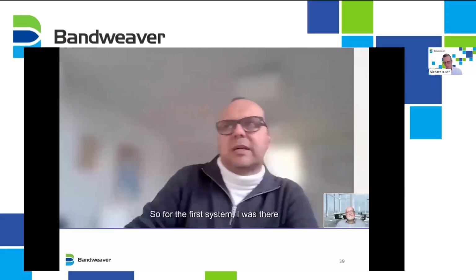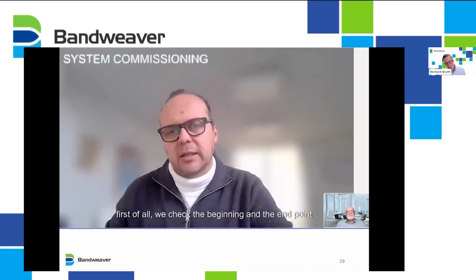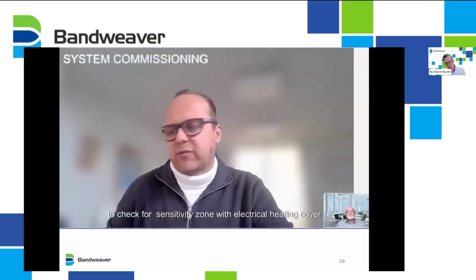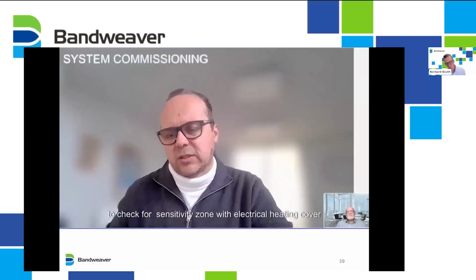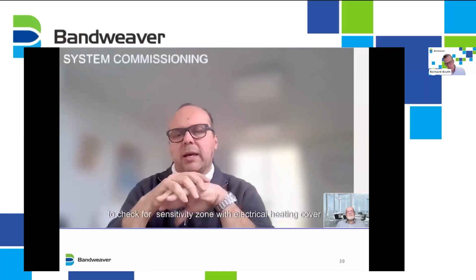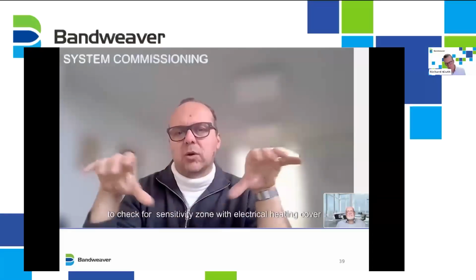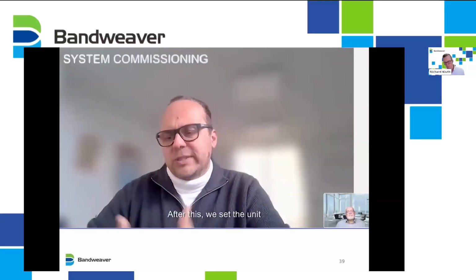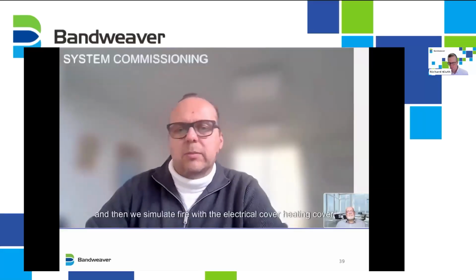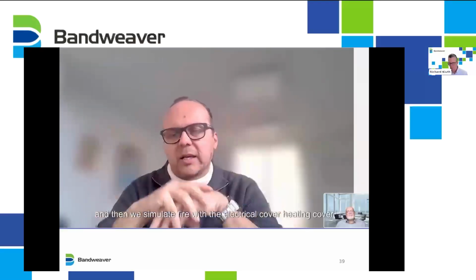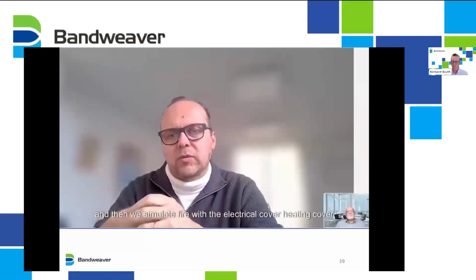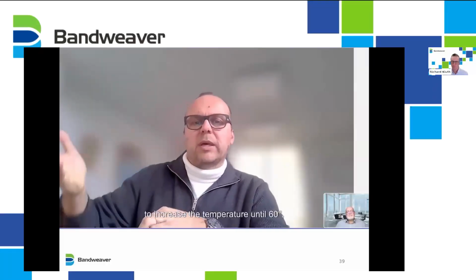For the first system, I was there. First of all, we check the beginning and the end point to check the sensitivity zone with an electric cover, a heating cover. After this, we set the unit and then we simulate, let me say, fire with the electric heating cover, to increase the temperature up to 60 degrees.